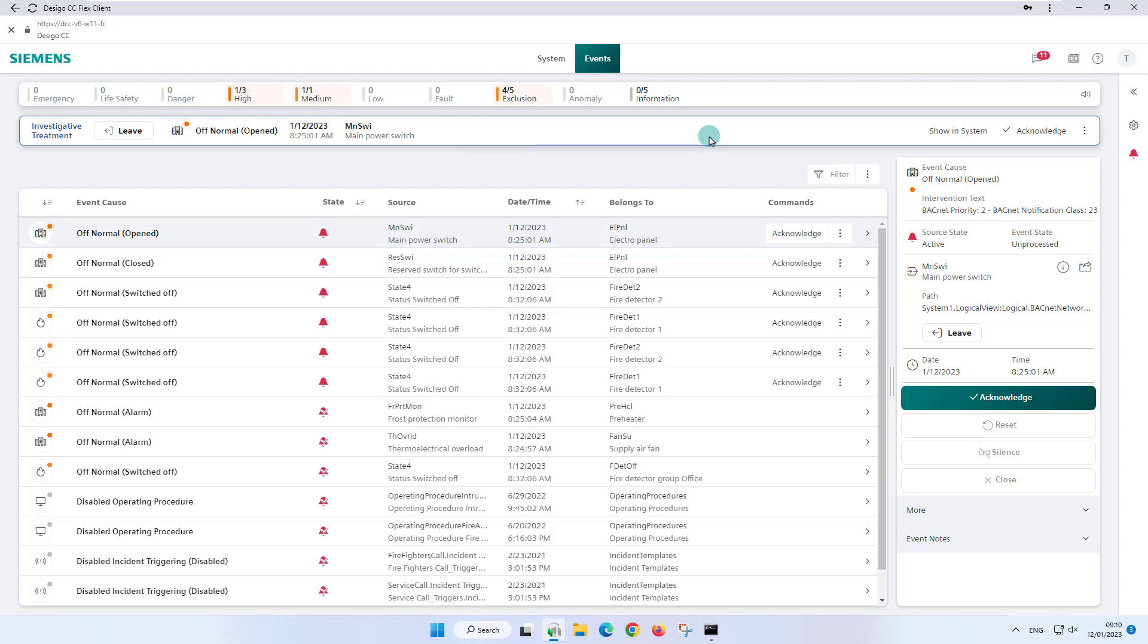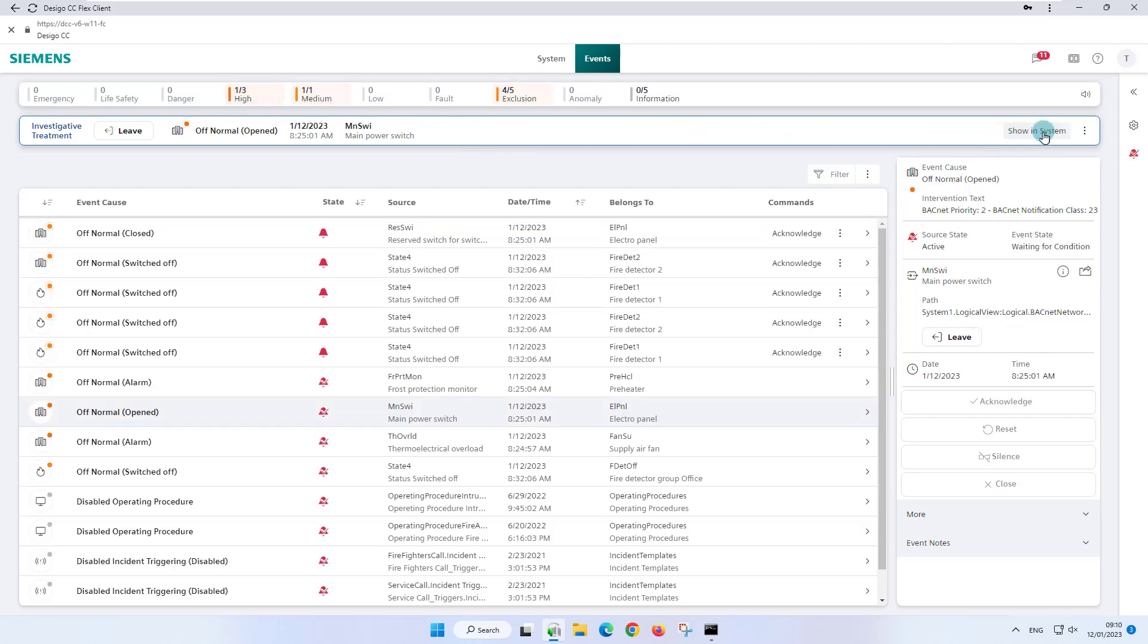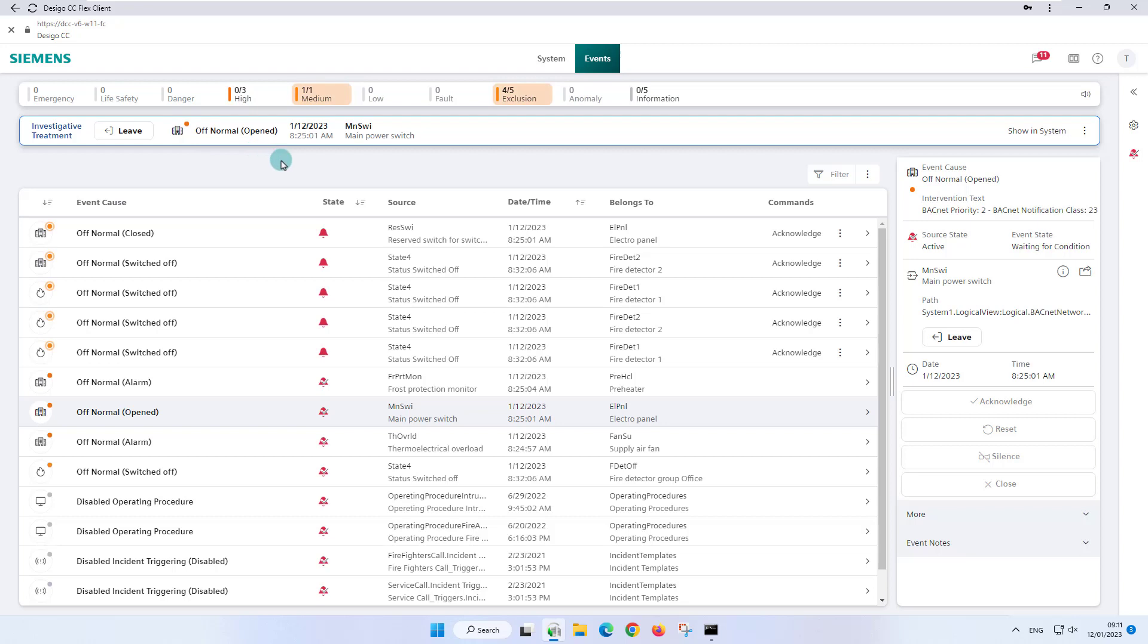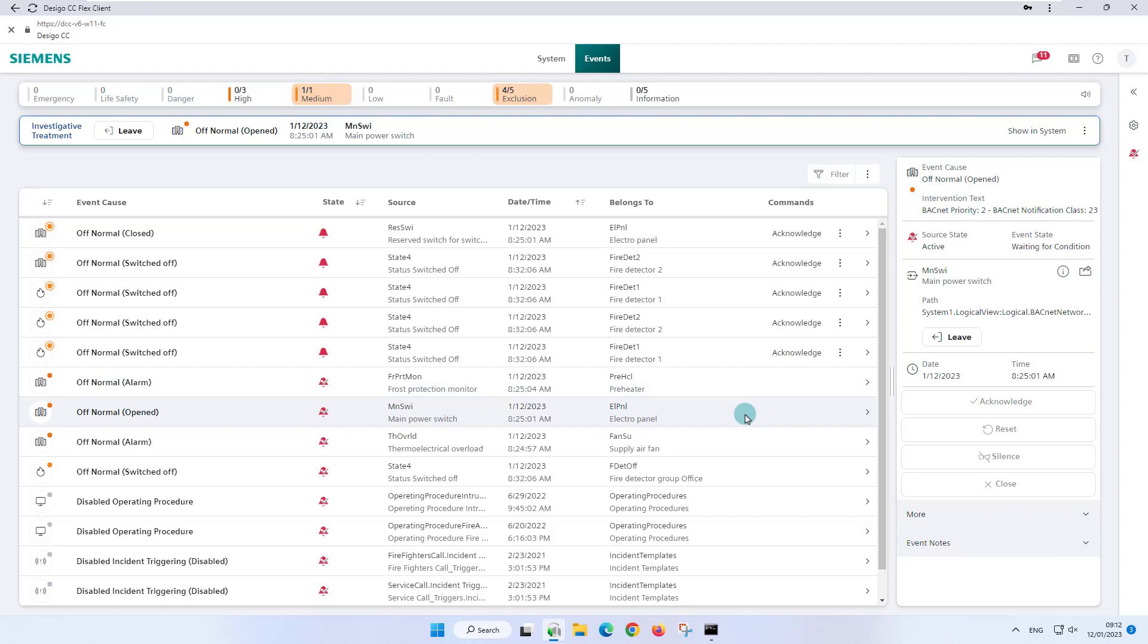We start with event handling and use the acknowledge option in the bar, since command execution is new in this location. In the investigative treatment bar, the alarm symbol no longer flashes, but is now a solid color. No further commanding options are displayed for event handling because the fault is not yet resolved, which is confirmed with the event state waiting for condition in the event details. The alarm is still selected in the event list and is now listed further down due to the acknowledgement. The high event lamp information in the summary bar has changed to zero unprocessed and a total of three events.